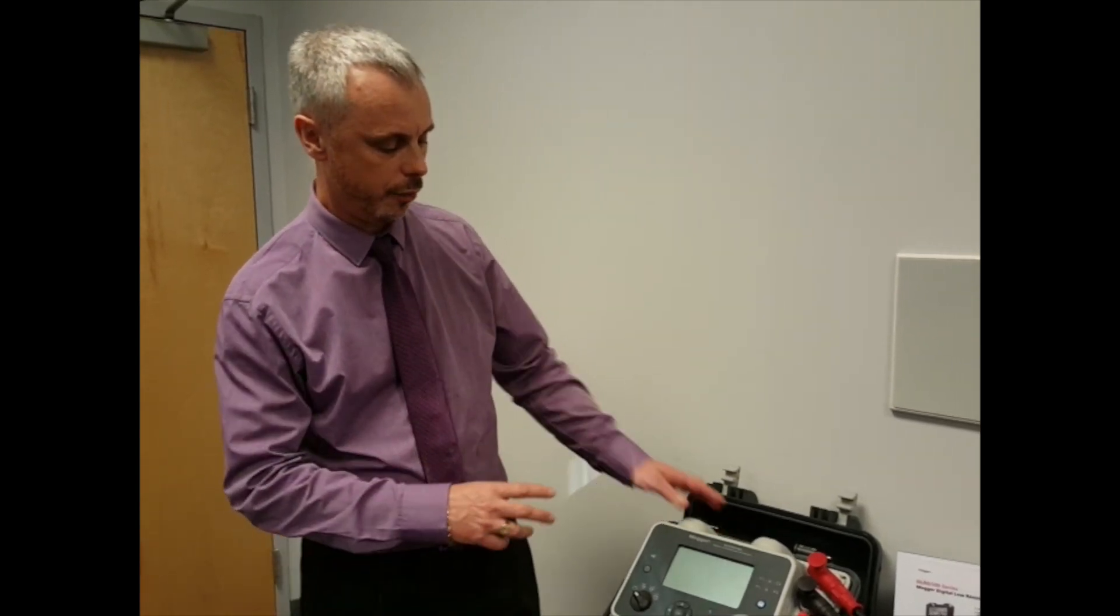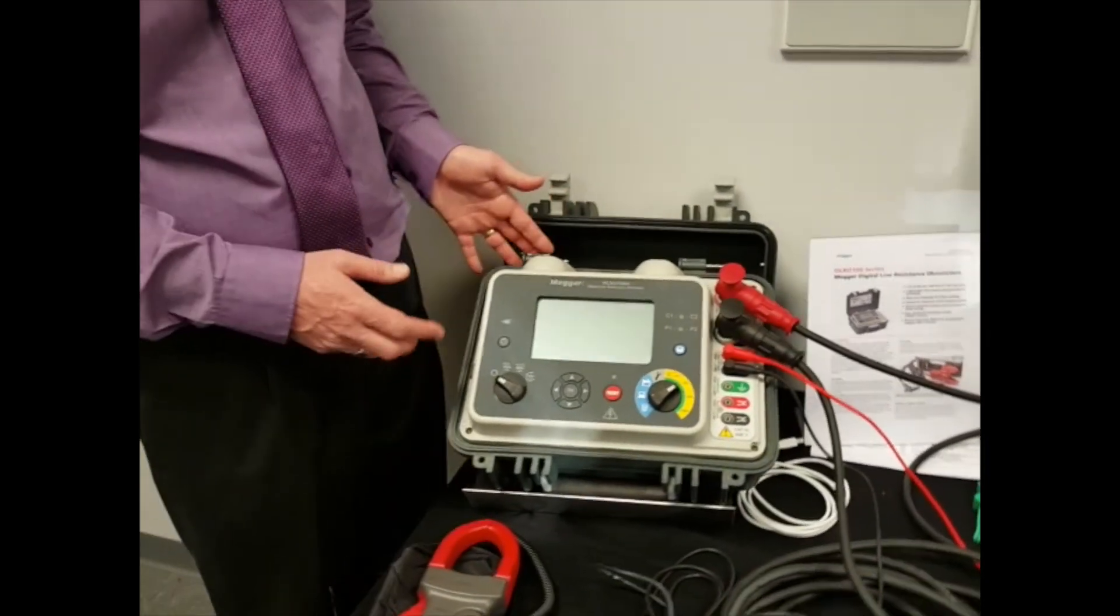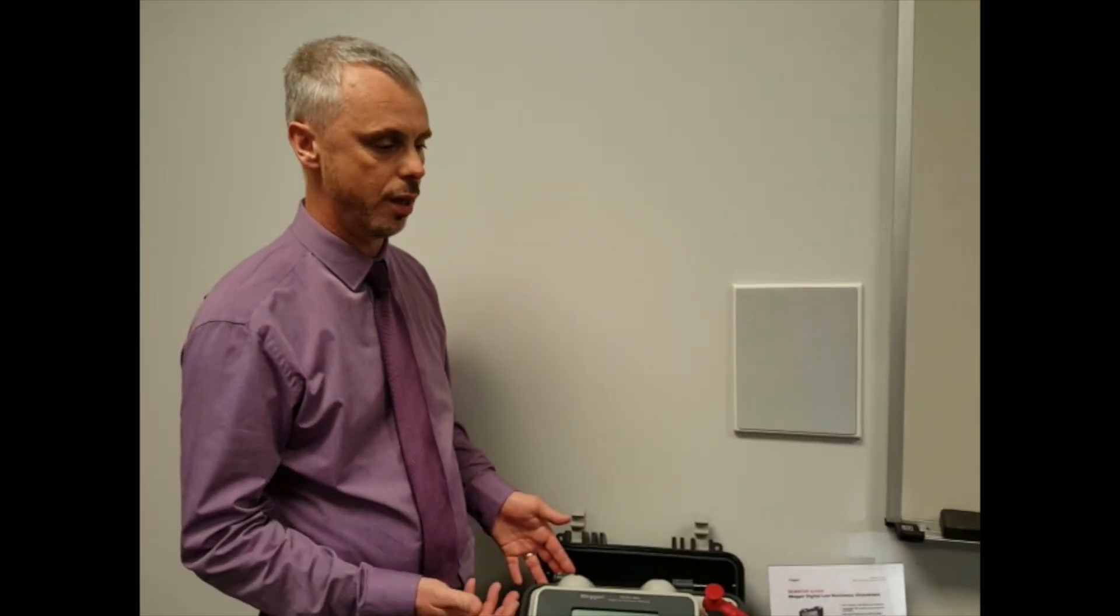The unit itself, once it's on the battery power, can operate for 20 minutes in total at 100 amps. That's two lots of 10 minutes testing. So it can maintain 100 amps for 10 minutes and you can do that twice on one charge.